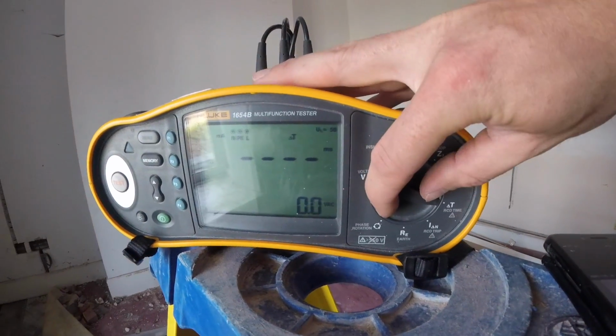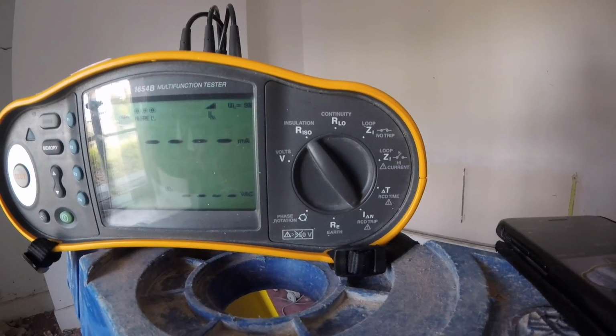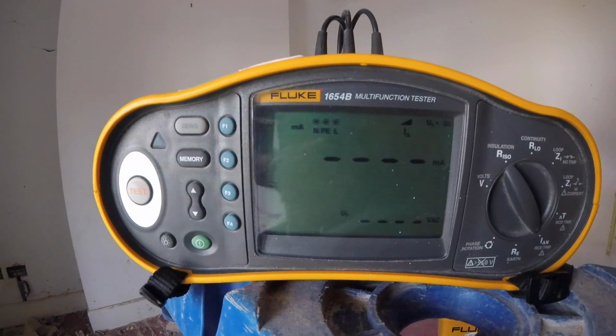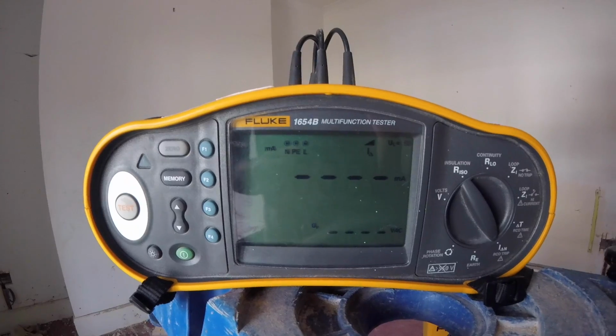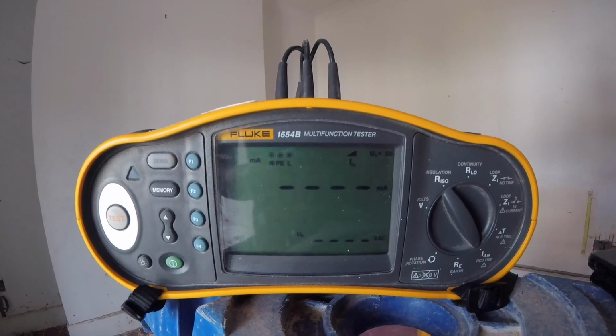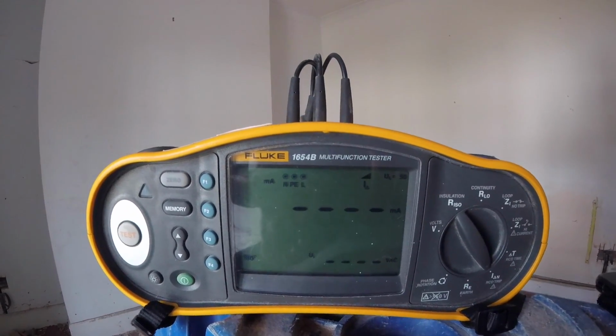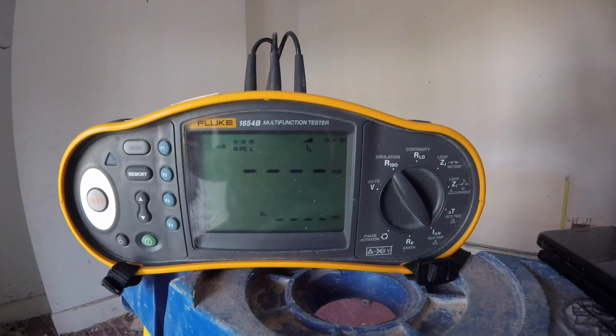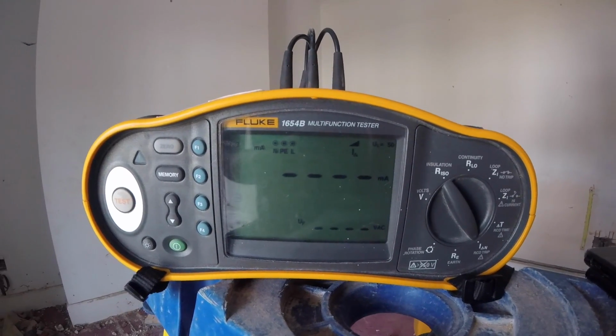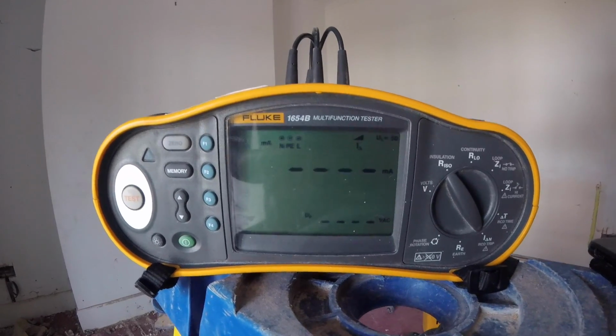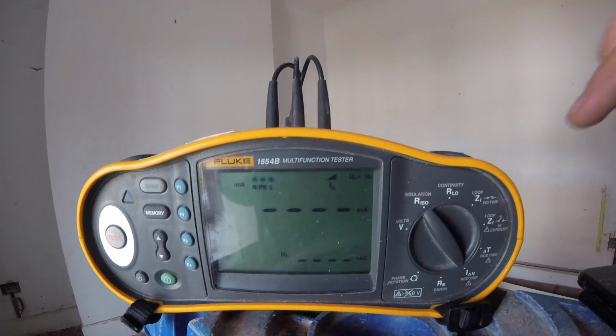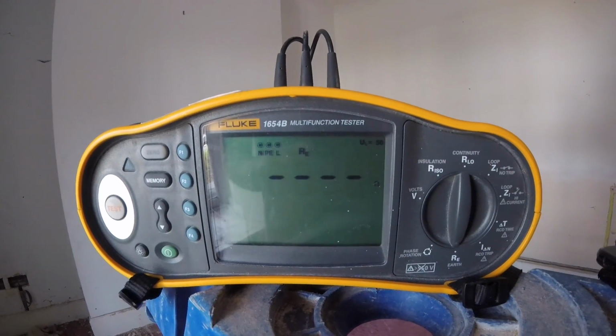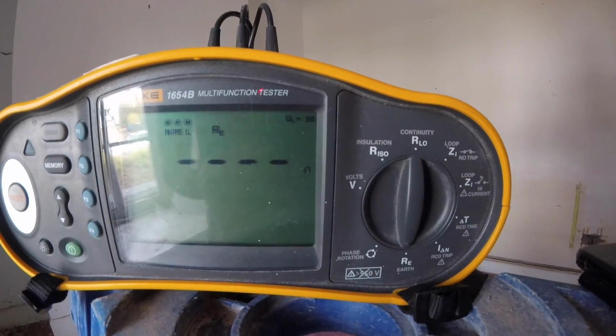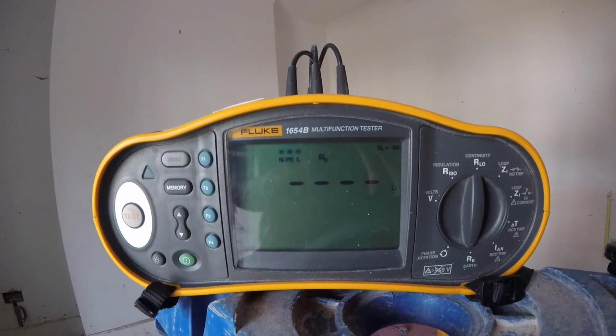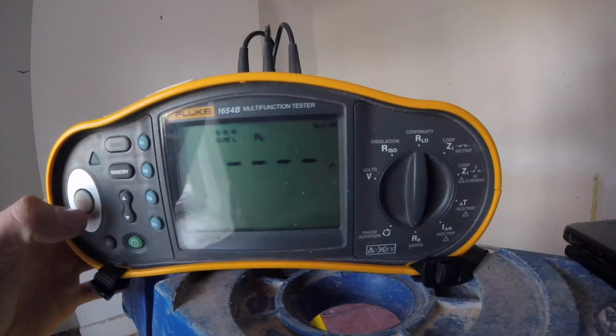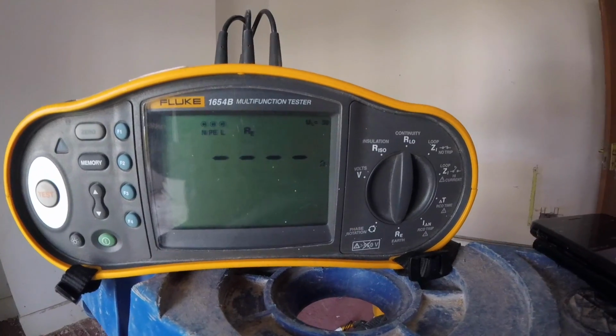Again, while I'm on the subject of RCDs, next test is the RCD ramp test. Again, that's quite good for seeing at what milliamps the RCD will actually trip at. If you've got a fault maybe on the circuit and you think you might have a sensitive RCD, that is a test to use, and that will ramp up the milliamps until it does trip, and it will display it on there. And then you have your RE test, which is your earth electrode test. I haven't actually got the probes for that, but that is very good. That'll literally just measure the resistance of your earth electrode.